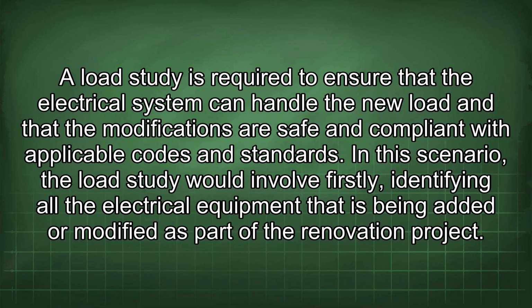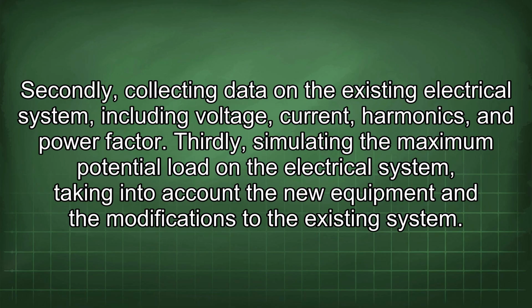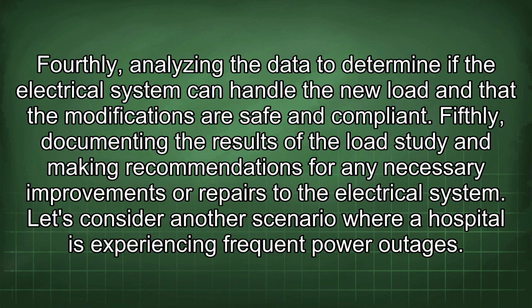In this scenario, the load study would involve, firstly, identifying all the electrical equipment that is being added or modified as part of the renovation project. Secondly, collecting data on the existing electrical system, including voltage, current, harmonics, and power factor. Thirdly, simulating the maximum potential load in the electrical system, taking into account the new equipment and the modifications to the existing system. Fourthly, analyzing the data to determine if the electrical system can handle the new load and that the modifications are safe and compliant. Fifthly, documenting the results of the load study and making recommendations for any necessary improvements or repairs to the electrical system.